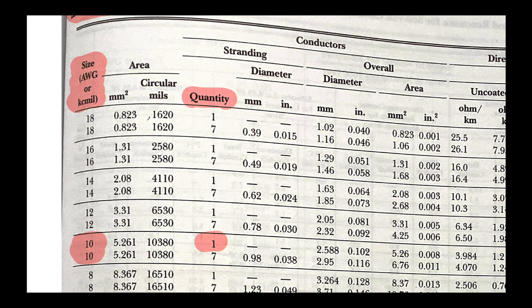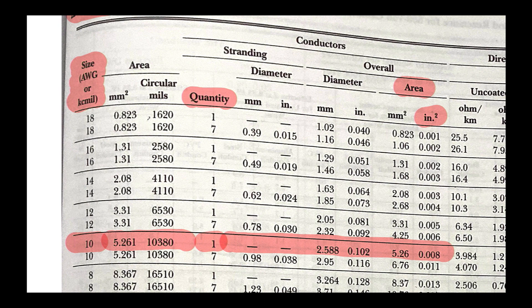Now we look for the area — and again we're looking for inches squared, not millimeters squared, so don't let that mess you up. I'll draw a line all the way across so we can see this more easily. At the intersection of the area column for square inches and 10 AWG bare conductor, we see the answer is 0.008 square inches.